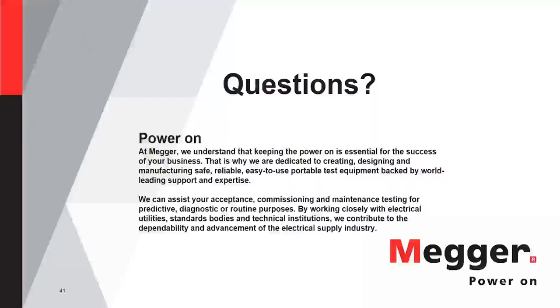Okay, that is quite an interesting question, because it's not very specific in the table. The way we see it is that you need to do the ohmic testing every 6 months, and whenever you hit the 3 calendar year testing, you have the option to do ohmic testing or capacity testing. So yes, kind of a straight answer. You still need to do it every 6 months, but where you have the option to select one or the other is every 3 years. And I guess once you start doing one thing, you keep doing that one, and you don't need to change on that.